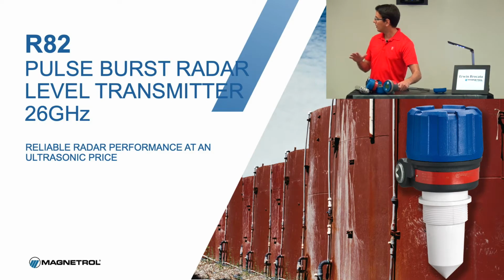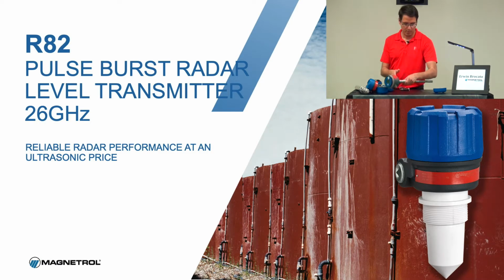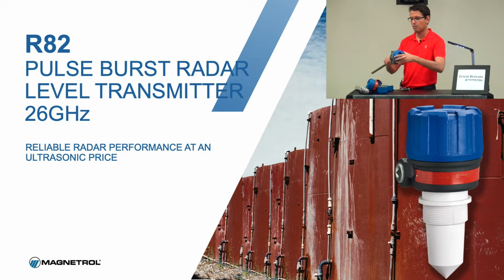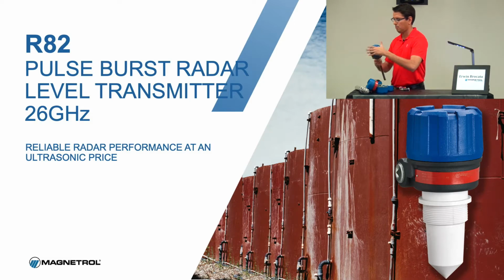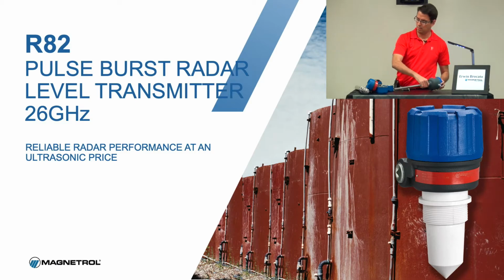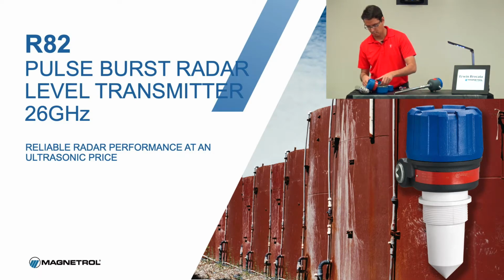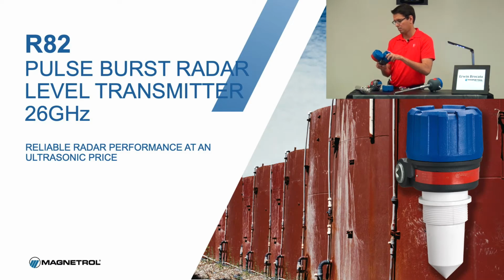Erwin, to that point, like the single compartment housing, right? So if you have something like, say, ammonia gas, and this is very suited for ammonia refrigeration applications. Yes. You might need a secondary seal. So there's only one seal in the 700, but you could add a seal to the conduit. Adalet and Crouse-Hinds and companies like that make a secondary seal that you can put in the conduit, so that if the transmitter did fail, the ammonia wouldn't back up into the wiring in the conduit. So that's all I have, Erwin. Good. All right, thank you very much.